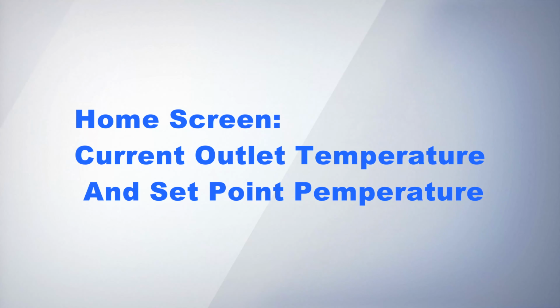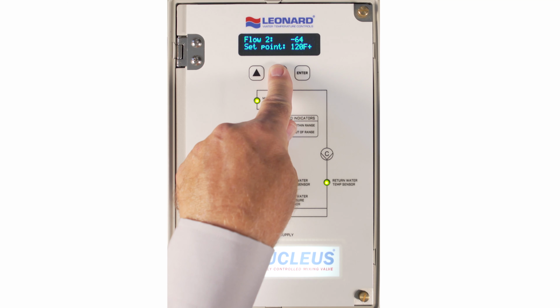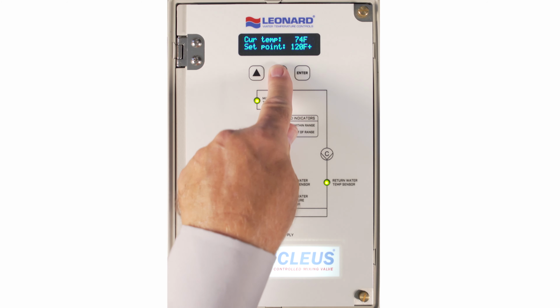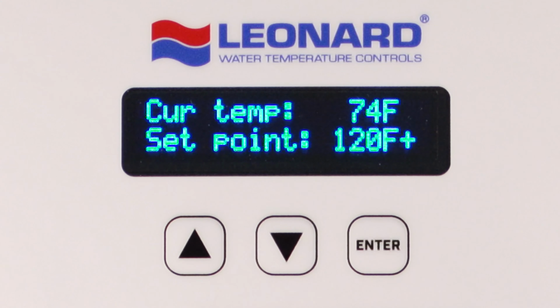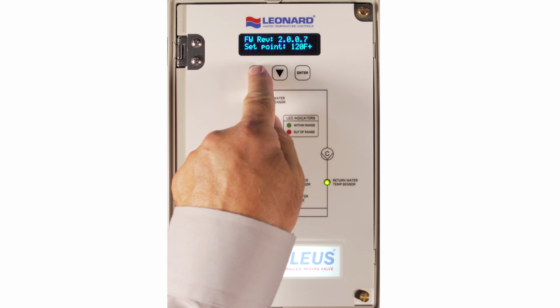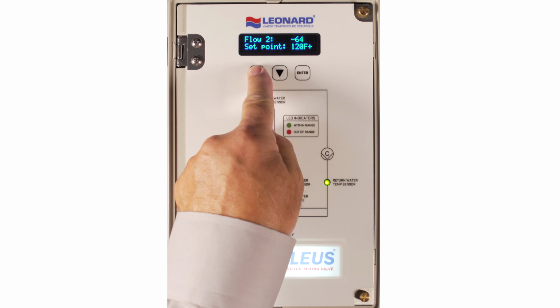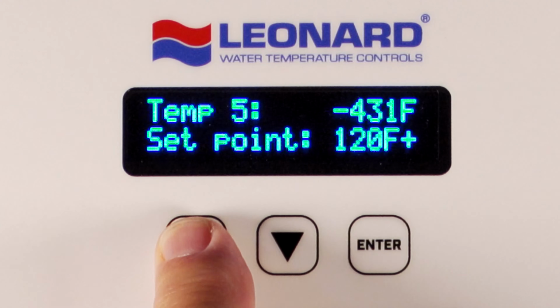Home screen. Current outlet temperature and set point temperature. Pressing down 17 times displays current temp, F or C. The user is returned to the home screen, which displays the current temperature as measured on valve outlet T3 and the set point temperature on the line below. Note: a large negative value displayed at the current temp line indicates the sensor is damaged or not properly wired to the main control board. Pressing the up key will reverse the order previously shown and allow the user to scroll through the above menu items in reverse order.